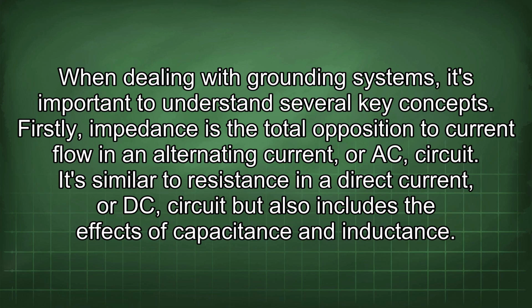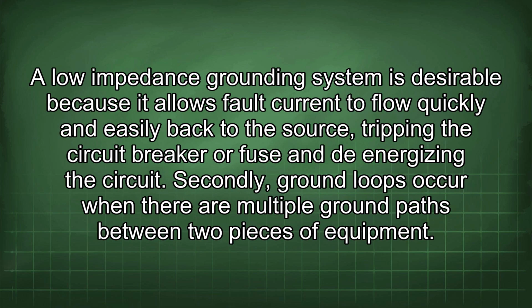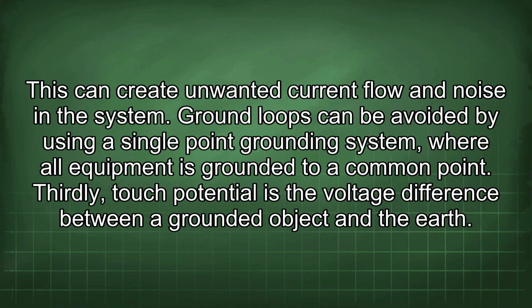Firstly, impedance is the total opposition to current flow in an alternating current, or AC, circuit. It's similar to resistance in a direct current, or DC, circuit, but also includes the effects of capacitance and inductance. A low impedance grounding system is desirable because it allows fault current to flow quickly and easily back to the source, tripping the circuit breaker or fuse and de-energizing the circuit. Secondly, ground loops occur when there are multiple ground paths between two pieces of equipment. This can create unwanted current flow and noise in the system. Ground loops can be avoided by using a single-point grounding system where all equipment is grounded to a common point.